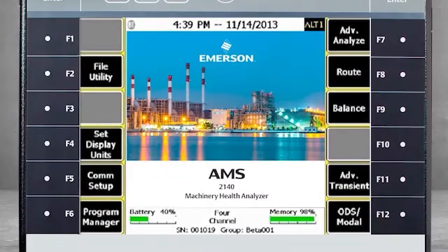Let's see how to accomplish this using the AMS 2140. First thing we will do is collect regular data using the normal averaging process to create a spectrum which contains both synchronous and non-synchronous information. In our example, we'll be measuring at 50 Hz on an electric motor, and we'll see a significant peak at 2 times the line frequency. 2 times line frequency is actually 100 Hz, which is non-synchronous data and is the normal average present in the stored data. But when we apply synchronous analysis, the 100 Hz will disappear. Let's take a look.